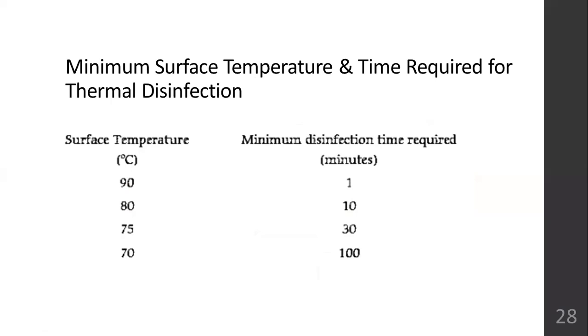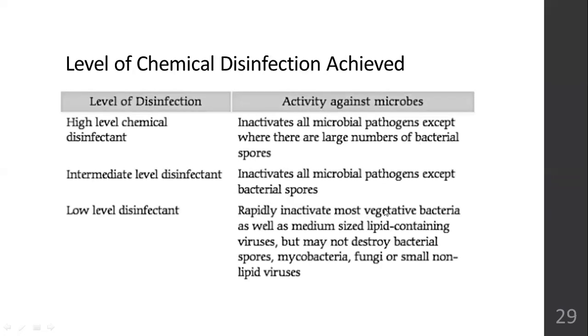Regarding surface temperature, when the temperature is high, you don't have to keep the item for a long time. Here you can see when the temperature is 90 degrees Celsius, the minimum time of disinfection required is just 1 minute. As soon as the temperature goes lower, like 70, you have to keep the item for 100 minutes. That is more than an hour, approximately 1.5 hours. So the higher the temperature, the less time is required for disinfection.